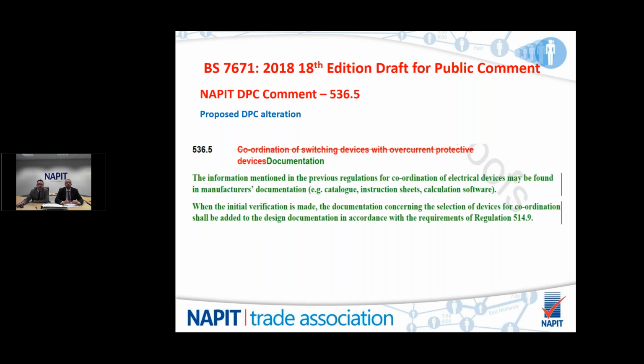So, the next proposed DPC alteration, 536.5, used to be called coordination of switching devices with overcurrent protective devices. It's now just documentation. And another innocuous one, it's asking for information mentioned in the previous regulations for coordination of electrical devices and various documentation, manufacturers' documentation, etc. It's asking that it shall be added to the design documentation in accordance with the requirements of Regulation 514.9. That's not strictly true. Regulation 514.9 doesn't require design documentation to be appended to any verification or documentation at all. So we feel it's a little inaccurate, and changes need to be made to it to ensure that it's factual and is not misleading at all.